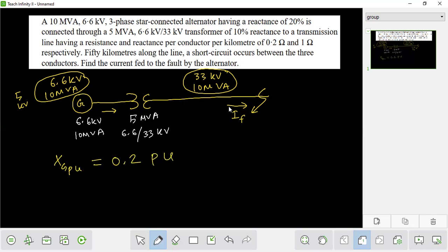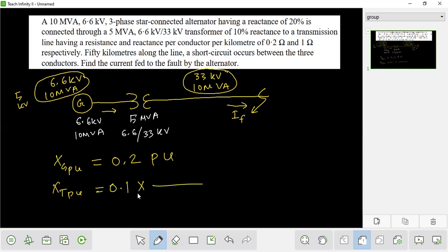So 0.2 per unit. For the transformer reactance conversion: 10% is 0.1. The formula is: X_new = X_old × (new kVA / old kVA) × (old base voltage / new base voltage)². New MVA is 10, old MVA is 5.